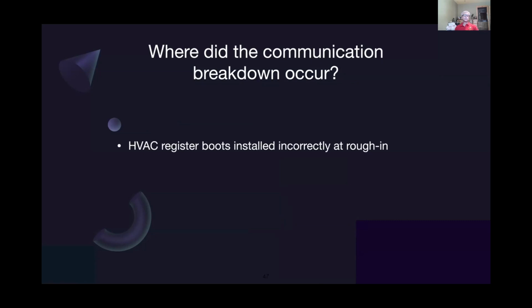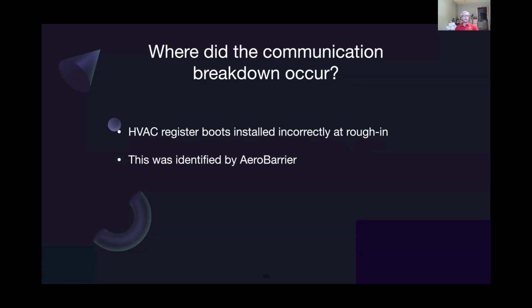The register boots were installed incorrectly at rough-in. What I mean by this is these were not supported on both sides. This was just the flanged ceiling HVAC boot to drywall connection, and they only nailed it onto one of the bottom chords of the truss. It should have been supported all the way across. This was identified by Aerobarrier, and that's where those photos came from.